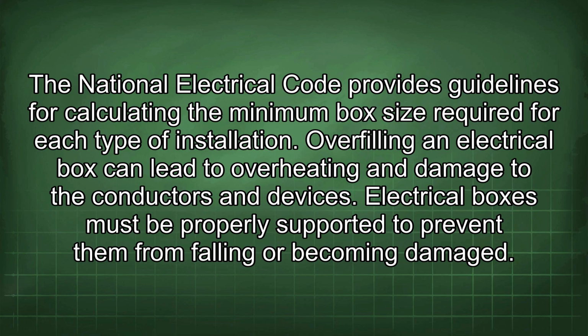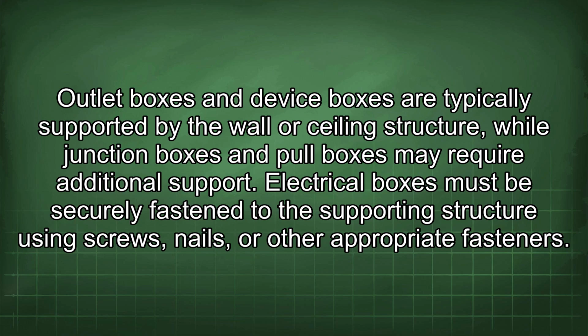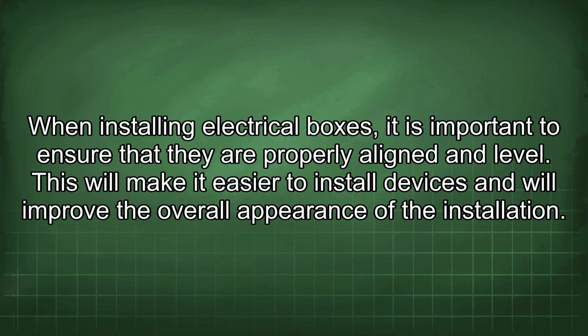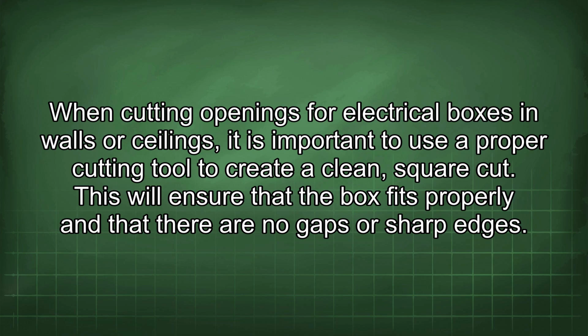Electrical boxes must be properly supported to prevent them from falling or becoming damaged. Outlet boxes and device boxes are typically supported by the wall or ceiling structure, while junction boxes and pull boxes may require additional support. Electrical boxes must be securely fastened to the supporting structure using screws, nails, or other appropriate fasteners. When installing electrical boxes, it is important to ensure that they are properly aligned and level. This will make it easier to install devices and will improve the overall appearance of the installation. When cutting openings for electrical boxes in walls or ceilings, it is important to use a proper cutting tool to create a clean, square cut. This will ensure that the box fits properly and that there are no gaps or sharp edges.